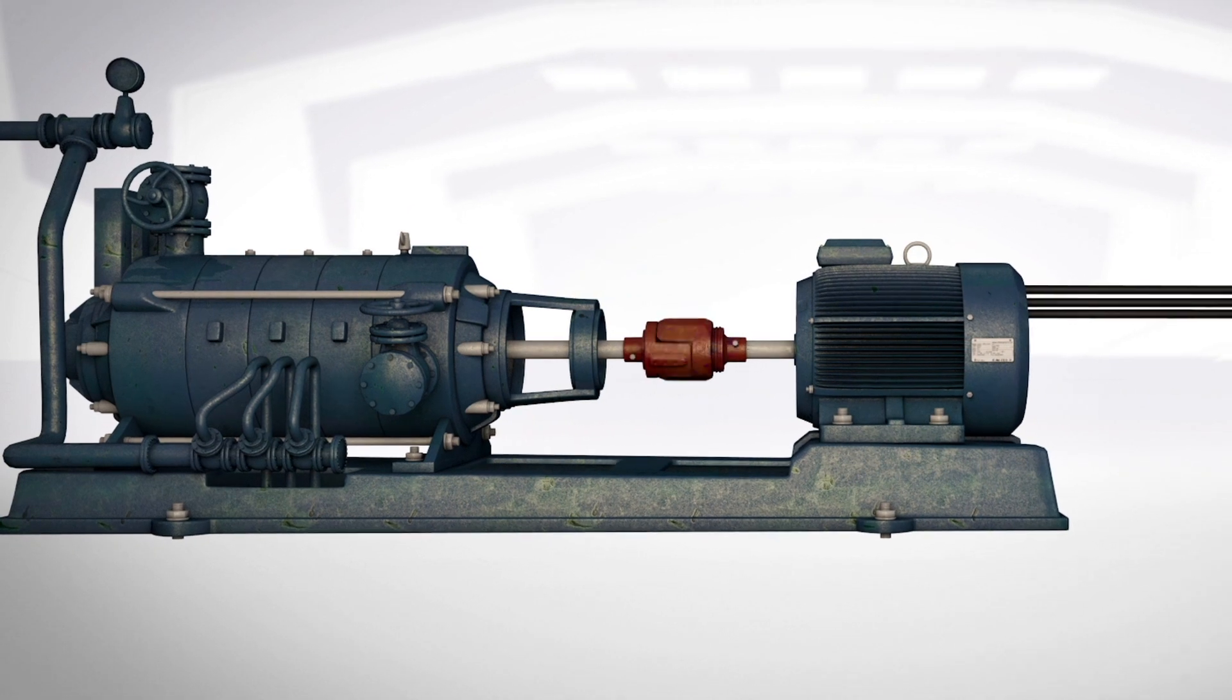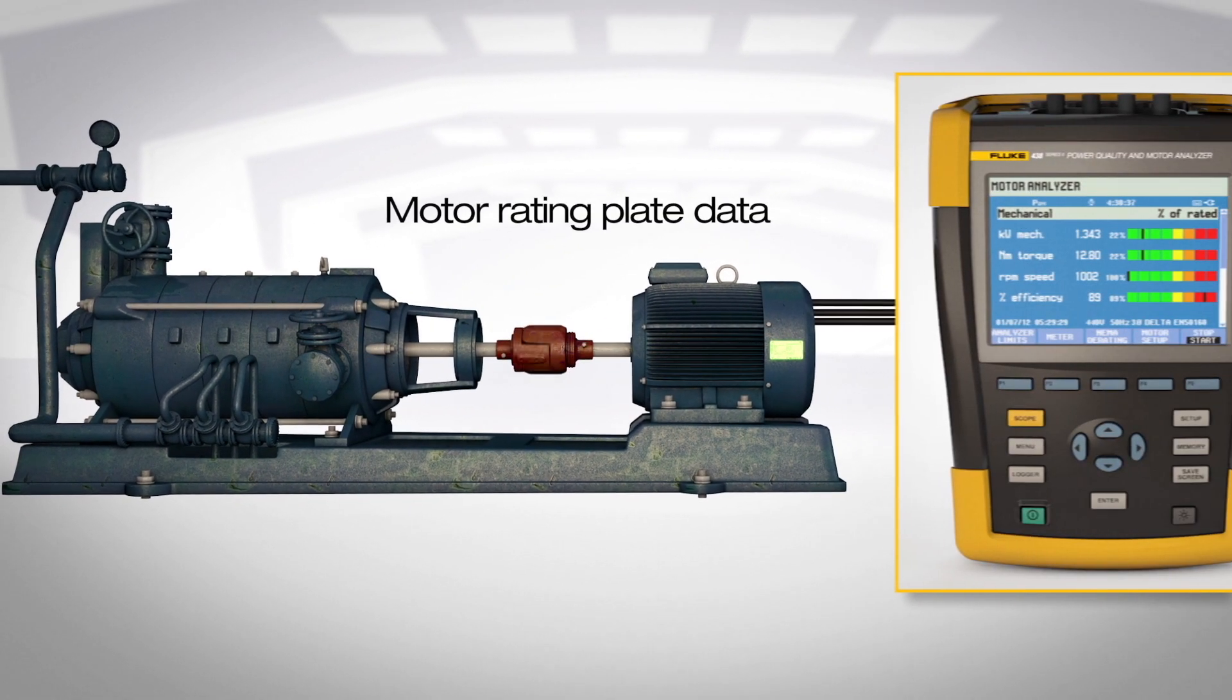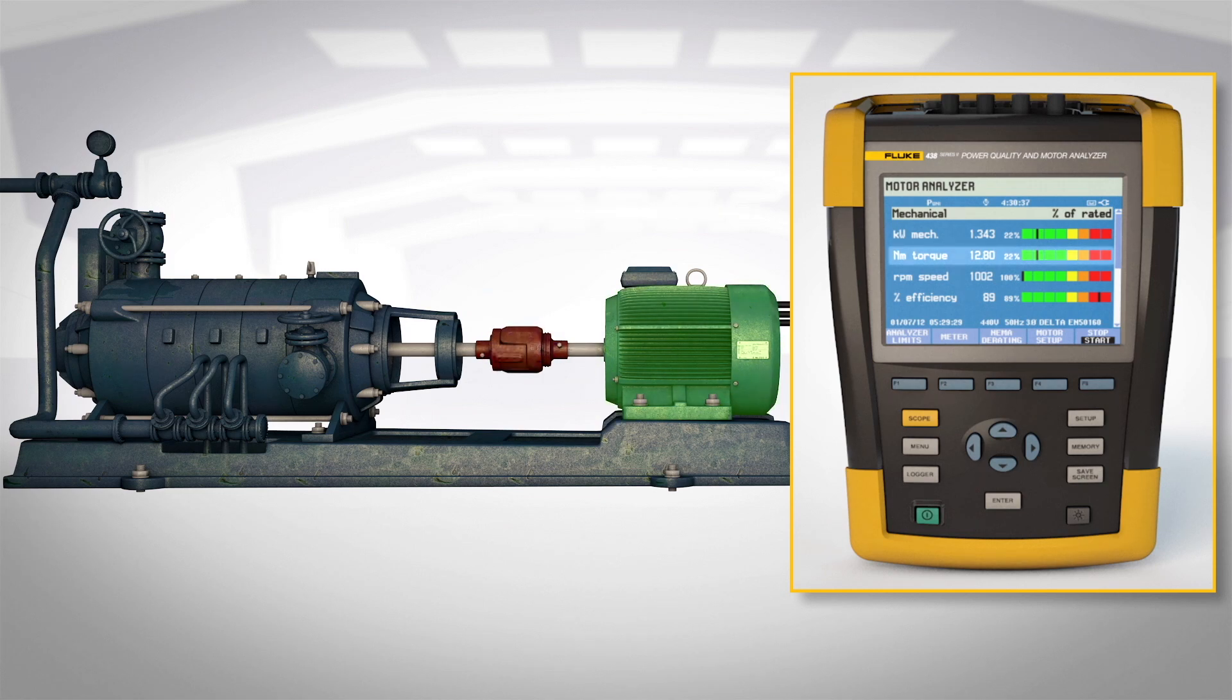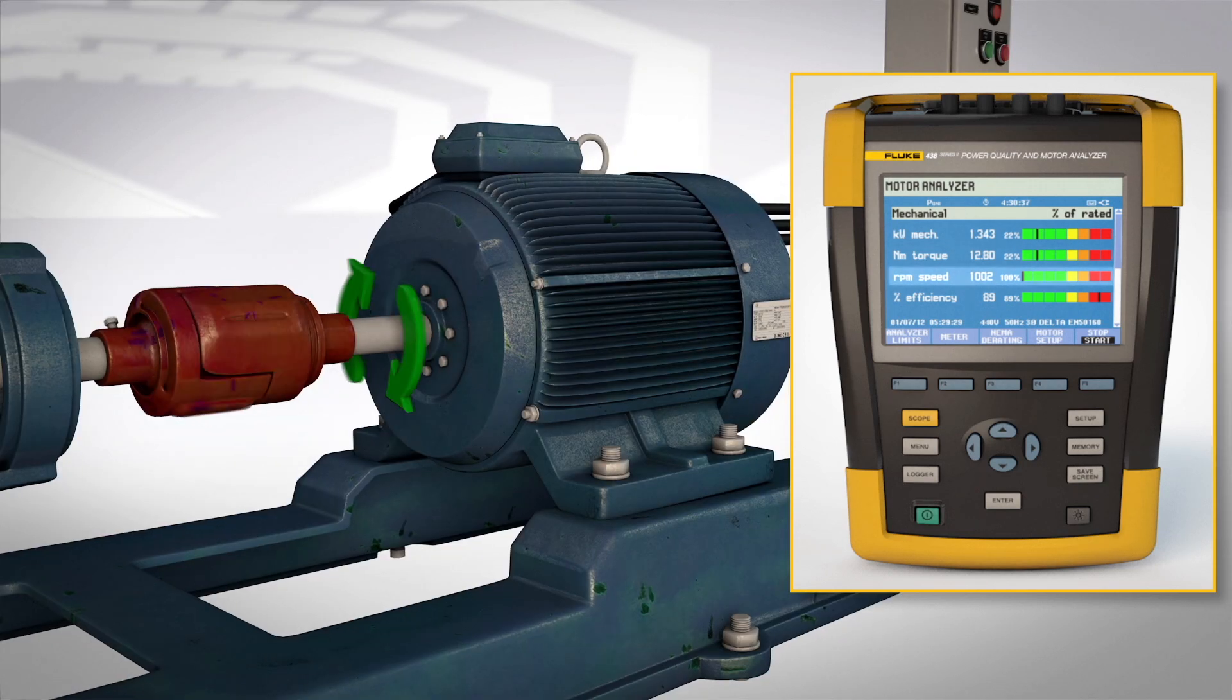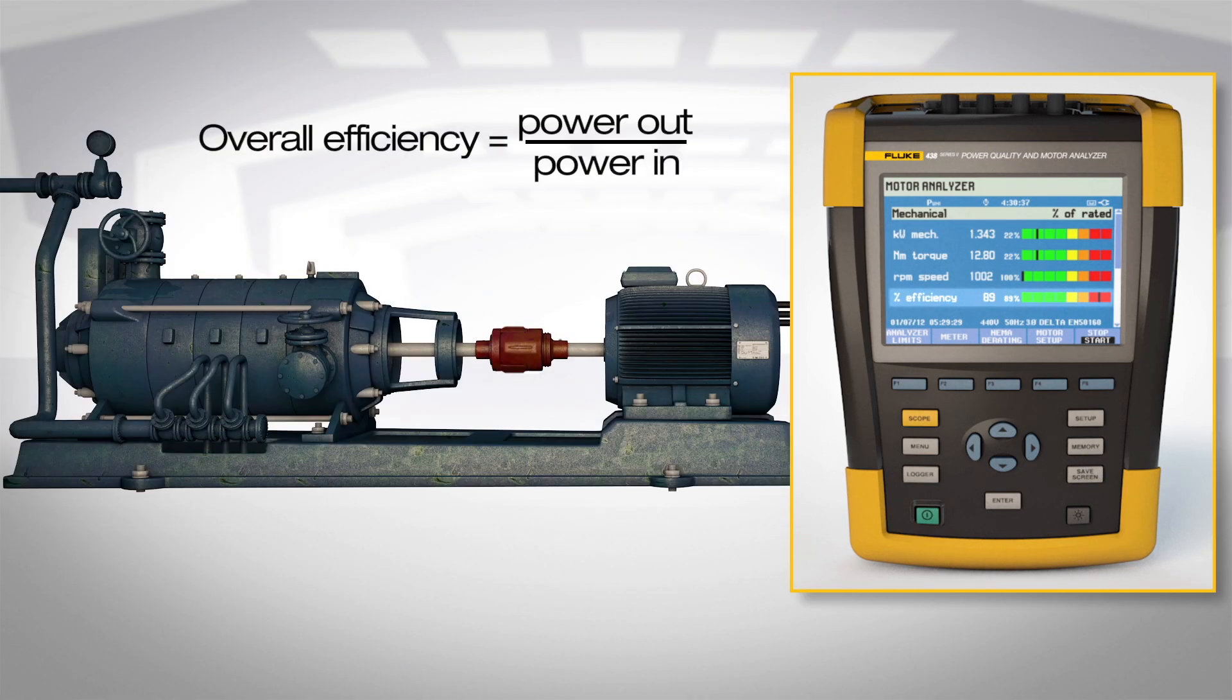Using three-phase electrical measurements on the input and motor rating plate data, the 438 calculates torque, the most critical mechanical performance variable, speed, load on the motor shaft, and overall efficiency without the need to install mechanical sensors.